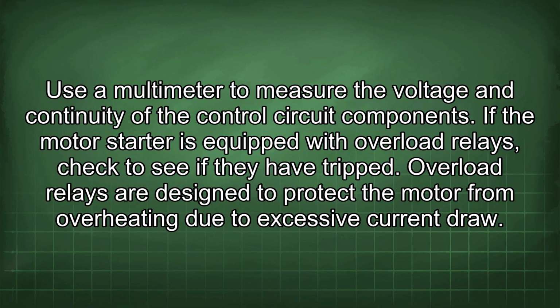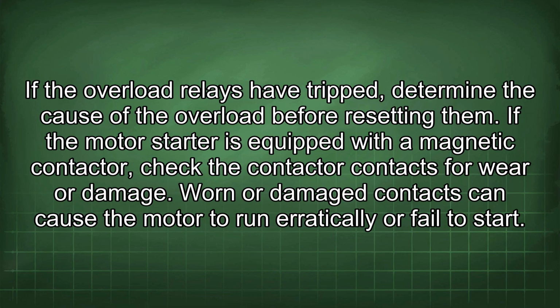If the motor starter is equipped with overload relays, check to see if they have tripped. Overload relays are designed to protect the motor from overheating due to excessive current draw. If the overload relays have tripped, determine the cause of the overload before resetting them.